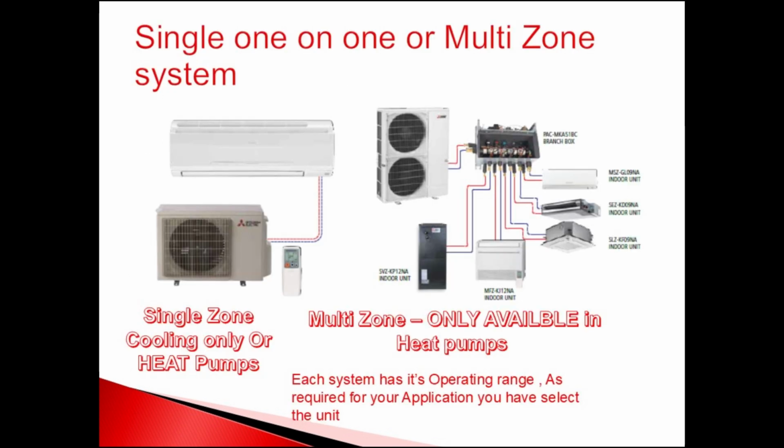A split unit can either be a one-on-one system, one outdoor unit with one indoor unit, or a multi-head system, one outdoor unit with multiple indoor units. One-on-one systems can be cooling-only units, but multi-head systems are only available as heat pump units.